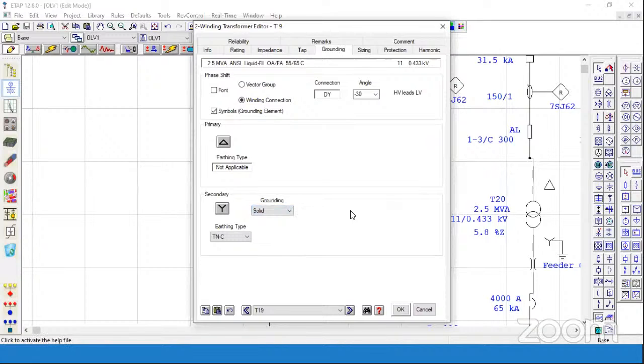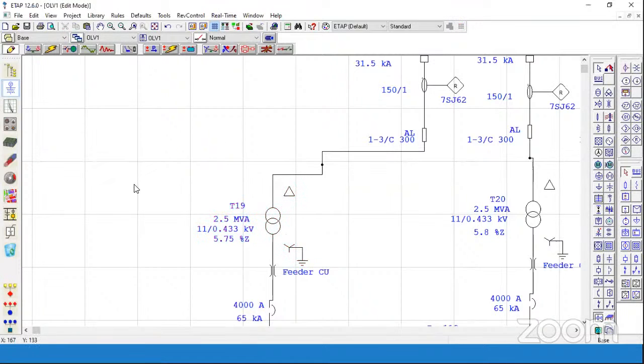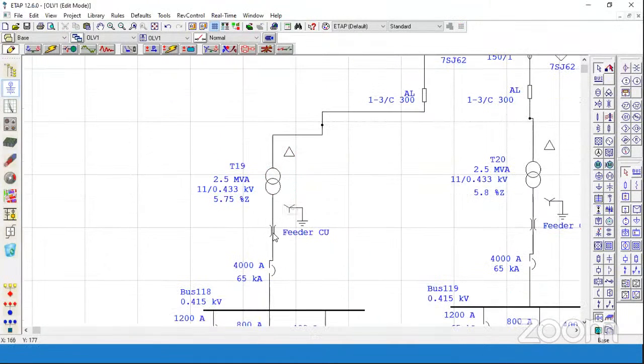And the vector group. What will be the vector group? As we have certain vector groups, here we can say Dy11, that is Dy and 11. The 11 is for the phase angle between the two windings, which is minus 30, meaning 11 in a clockwise direction. It's HV leads LV by 30°. Likewise, all these parameters of the transformers should be implemented.